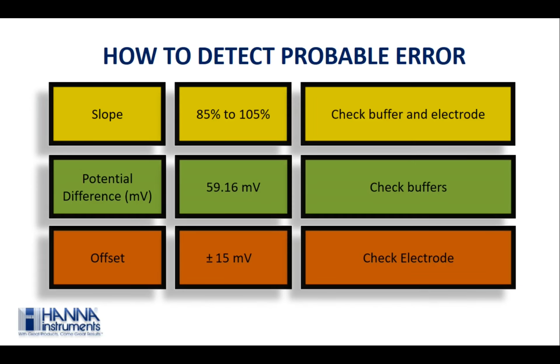Also, keep a note of slope and offset values every time you calibrate your electrode. You should also always note down the millivolt changes of all the stock buffer solutions at the time of opening it and gradually as you use it. You will understand when your buffer should be discarded and should not be used for calibration. Always note down the last millivolts of buffers to track the status of the buffer.